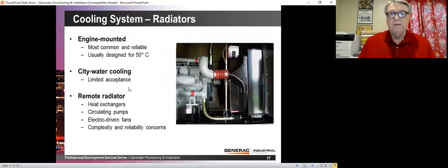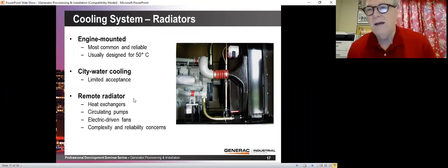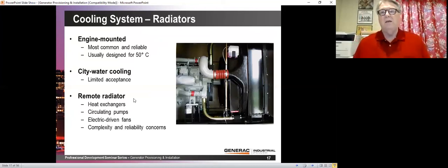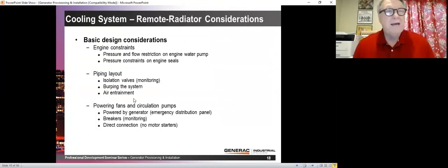Radiators, we won't talk about this a lot, but they're typically engine mounted. City water cooling that used to be appropriate years ago pretty much is gone. Now you can do a remote radiator that gets the heat away from the engine. Maybe you've got the engine inside of a building or even in a basement. You want to get that heat out. Sometimes you can put the radiator outside. This has gotten more and more problematic because on natural gas generators, typically you can't do it because of the EPA. It voids the EPA warranty. On diesels, you can, but you need to work carefully with the manufacturer because there are EPA restraints these days that didn't used to be the case.